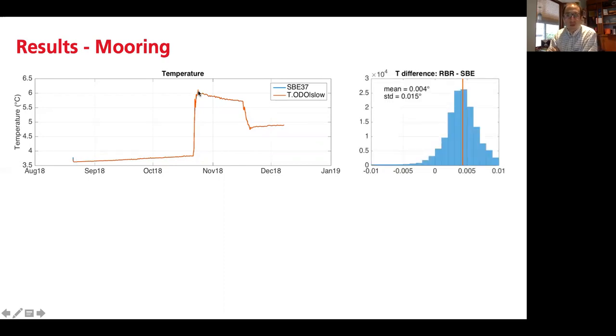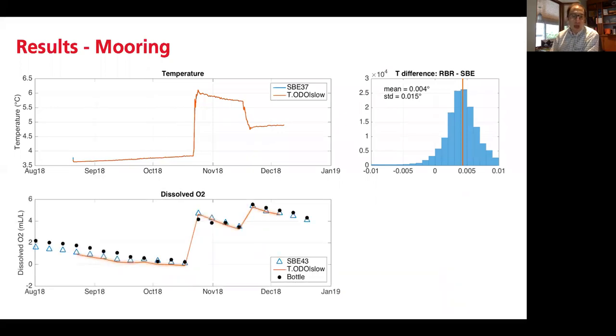If we actually do a measurement to compare the difference, you can see a nice tight histogram. The mean difference is 0.004 degrees Celsius, which is within the accuracy spec of plus or minus 0.002 for both the RBR and the Seabird. So we have good performance in temperature from both units. And now we'll look at oxygen. So the only oxygen measurement on the subsurface buoy was the RBR T.ODO. And that's in this red and orange line here.